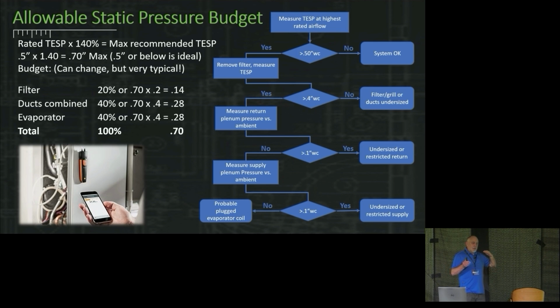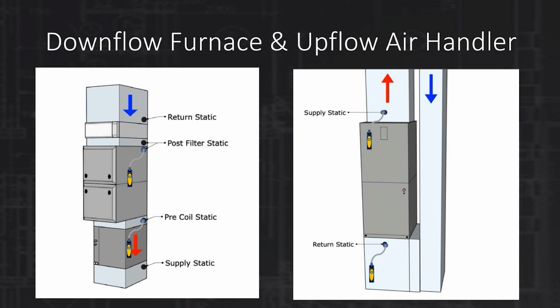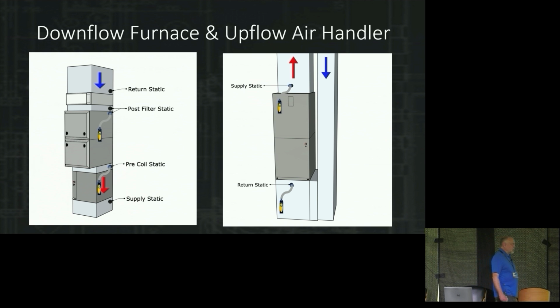So if you have a little bit higher restriction, let's say, of an evaporator coil, then you can put in a little bit lower restriction of a filter. Or you can fix a lot of problems on the return side of the system. A lot of times we'll just double up the return air side. So it doesn't matter where you spend your budget, it's just that you stay within it, right? That's the key thing here. Downflow, upflow furnaces, just a couple more showing where to measure the pre-coil static pressure. On an air handling unit, we actually do measure in the supply and the return, right? So a little bit different. So everybody in Florida, you've been doing it right. Everybody north of Florida that has furnaces, make sure you're in the right locations.